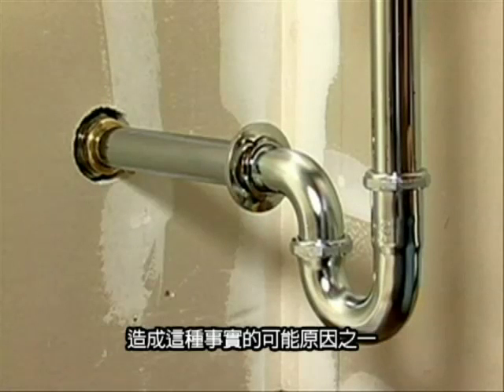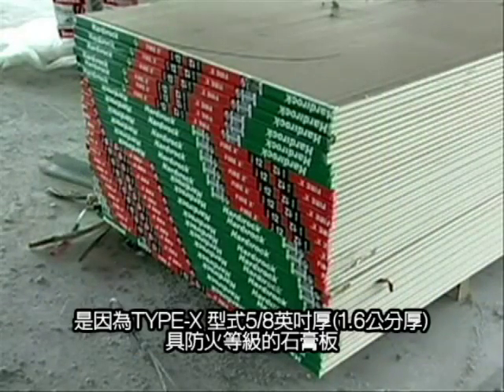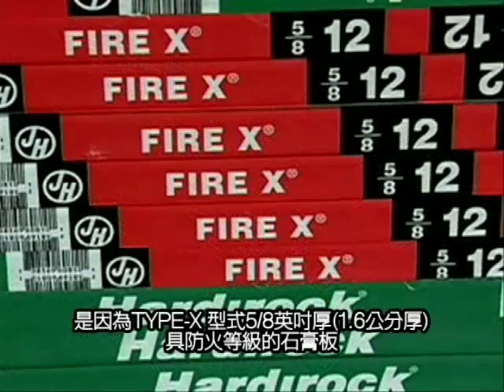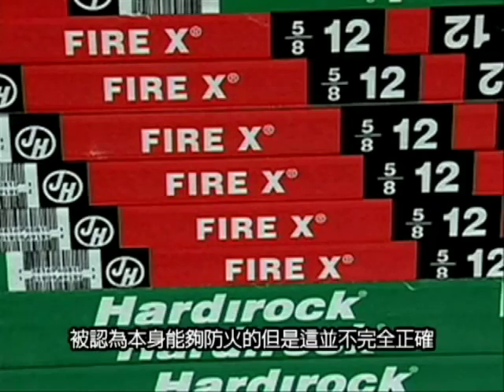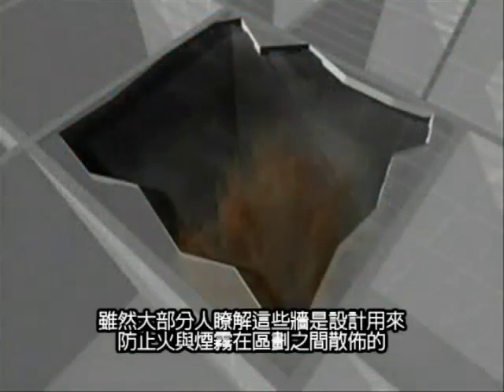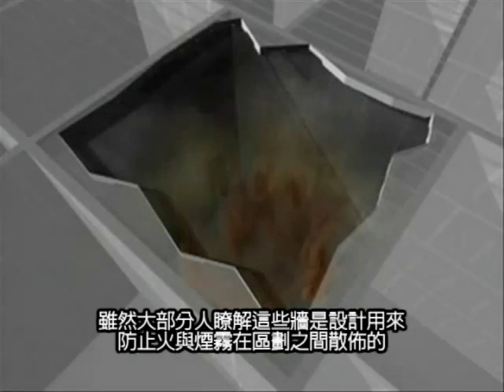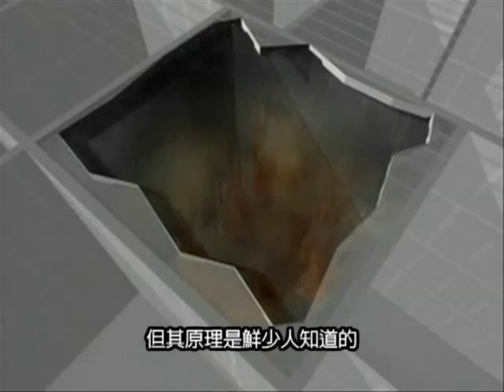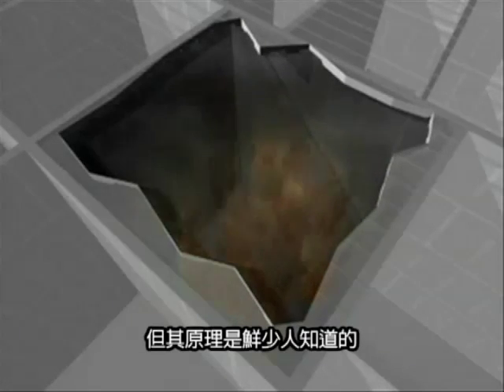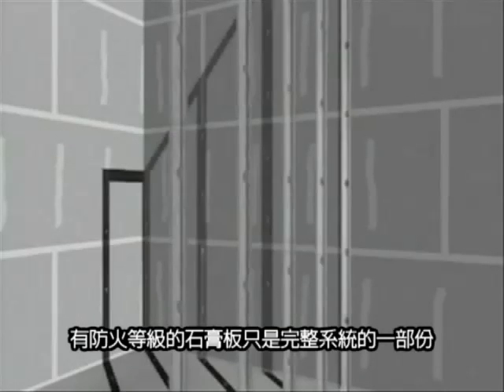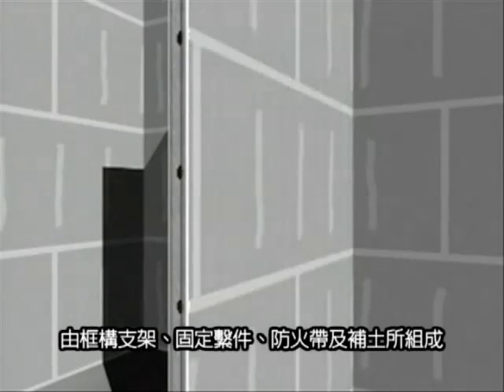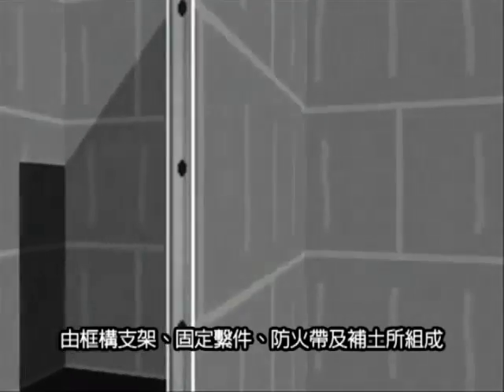Perhaps one reason for this stems from the fact that Type X 5/8" fire-rated gypsum board is thought to be fireproof by itself, which is not entirely accurate. While most people understand that these walls are designed to prevent smoke and fire from spreading between compartments, it's far less understood how this works. Fire-rated gypsum board is only one part of a complete system composed of framing members, fasteners, fire tape, and mud.